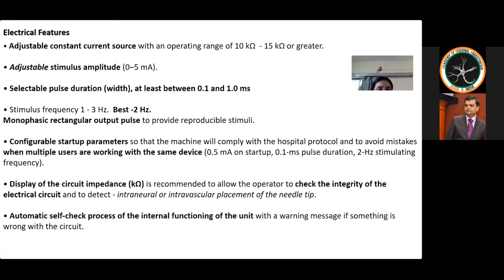Then the configuration startup parameters should be there so that the machine will comply with the hospital protocol and to avoid mistakes when multiple users are working with the same device. A display of the circuit impedance is recommended here to allow the operator to check the integrity of the electrical circuit and to detect a potential intraneural or intravascular leak. An automatic self-check process should be there for the internal functioning of the unit, with a warning message if there is any fault or disconnection in the circuit.